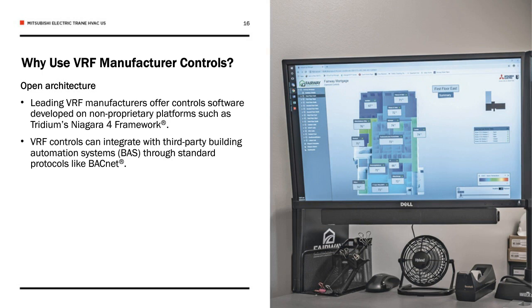The other answer is that you can use advanced controls and a control package that was created and put on by the VRF manufacturer. Mitsubishi does have one such program where it's actually monitoring the load that's required and the call from the indoor units, and it can decide based on almost a voting system whether or not the outdoor unit should be in the heating mode or the cooling mode. What it also will do is, if there is a call for both, it will provide those votes, and then it will maintain the heating mode for a specific amount of time, and then switch over to the cooling mode. And it will go back and forth based on the need.